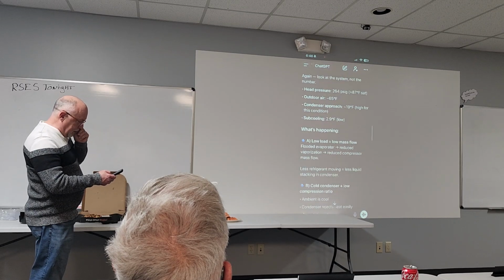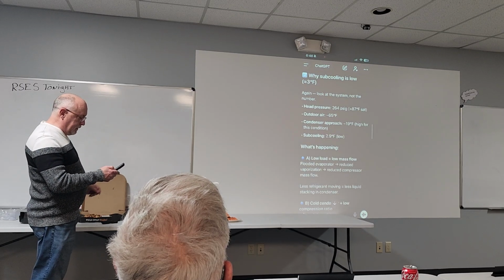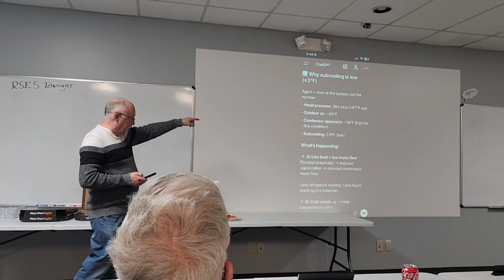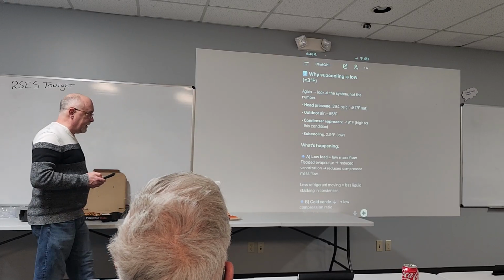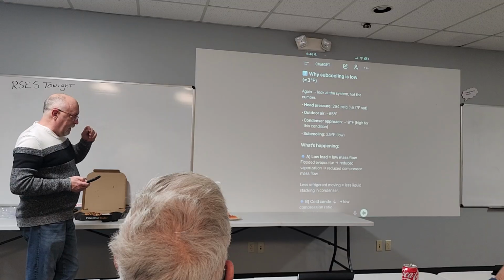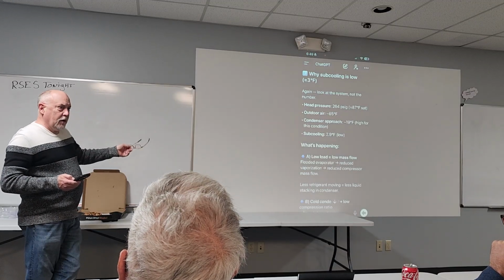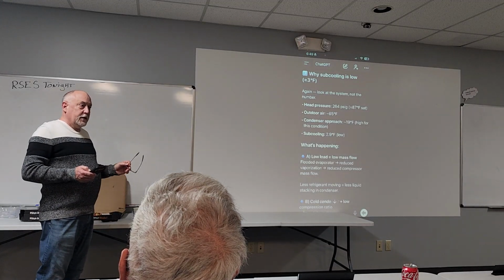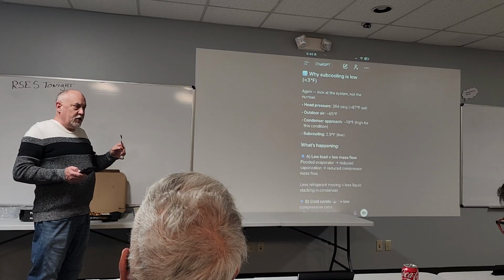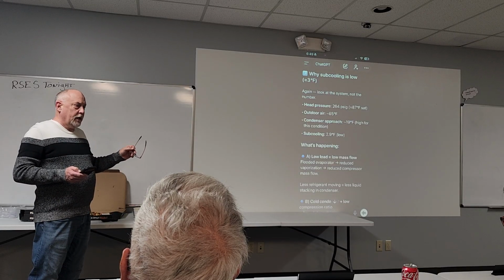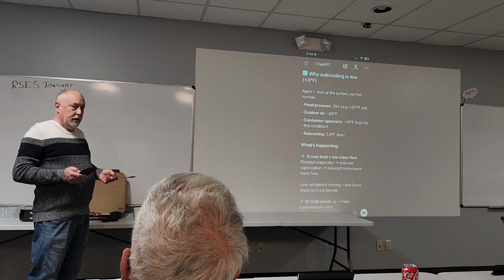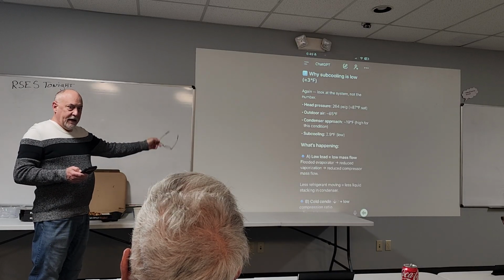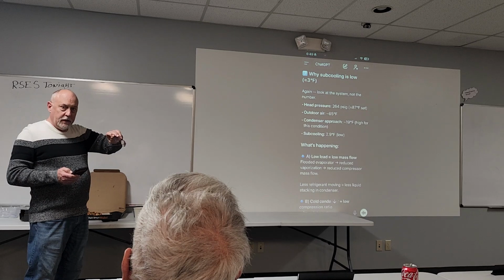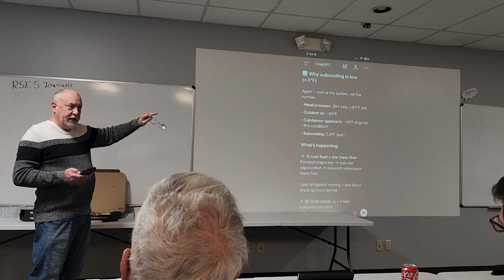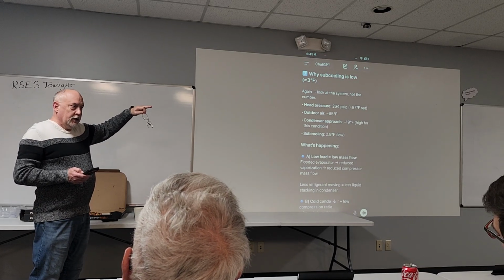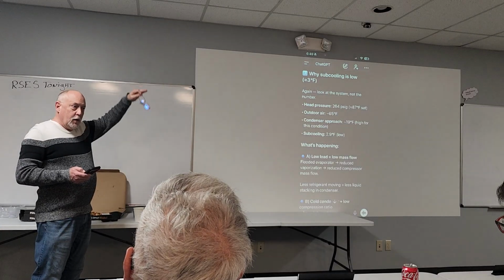Alright, went down a little far here. Alright, so again, let's look at the system, not the numbers. Outdoor air 65 degrees, condenser approach 19 degrees or higher for this condition, subcooling is low. Now, what's happening here? This is all a game of finding the refrigerant. If I have high head pressure and I have a fixed orifice system, where did I push all my refrigerant to? I pushed it from the condenser into the evaporator, because I'm increasing the condensing pressure. So I'm going to force more refrigerant through the metering device and flood my evaporator coil. If my superheat goes to 0, my evaporator coil is full.